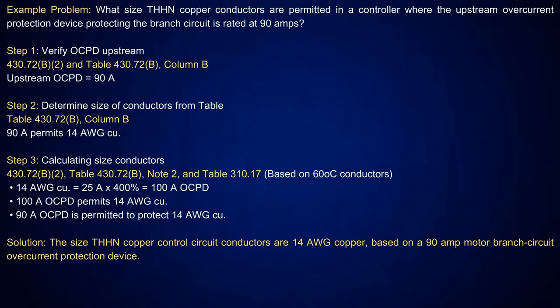Okay? Nice. And then this one, what this is going to get into, we're basically proving something here more than anything. And this is over in 430.72B2. Okay? And this is where they're going to get in. Like this first one we're going to talk about here, this is where they're sizing some THHN copper conductors that are permitted in a controller where the upstream overcurrent device protecting the branch circuit is rated 90 amps. Okay? So when you look at table 430.72B, column B, it's going to tell you 90 amps permits for number 14. But how do I prove that?